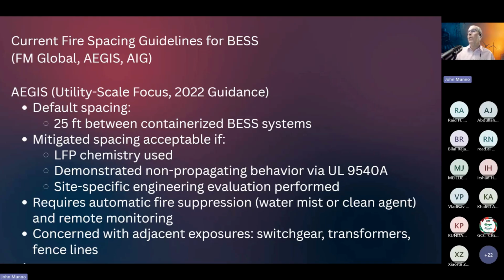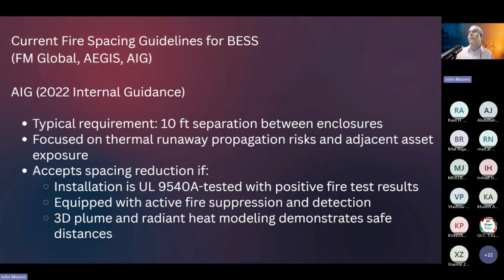I had a facility that was about 10 foot of spacing, and we were able to talk AEGIS into accepting that spacing. Now, that wasn't a typical BESS. It was a black start BESS. So it was there to help restart gas turbines that were there, believe it or not, to back up the wind out in Palm Springs, California. It's an 800 megawatt plant that has 8 LMS100 GE gas turbines, simple cycle gas turbines. They can start up in 10 minutes, but that's not quick enough for the grid. So we installed a BESS that will help support the grid, but mainly to get these gas turbines all up and running if there's a grid outage. But AEGIS would like to see actual testing on your configuration and your equipment before they're going to accept less than 25 feet. Just be aware of that if you ever get to working with AEGIS.